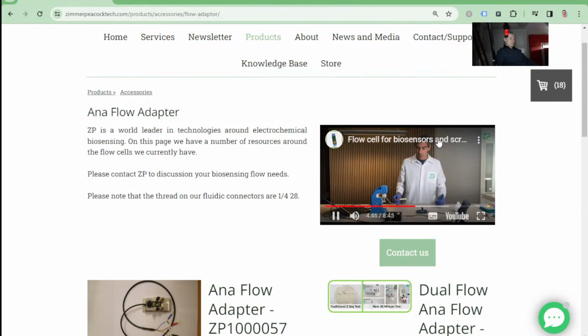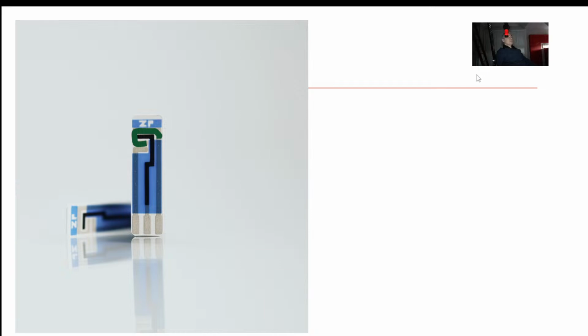So the quick answer to your question is most of our sensors, especially the ones we discussed today, including glucose, lactate, oxygen, sodium, potassium, urea, pH was in there as well, and I added ammonium in there, they're all able to be used in a flow cell. And yeah, the idea is that you would have a sensor in a flow system, flow the liquid over the top of it, and then have calibration routines. That's the way I would do it if I was trying to make a very accurate system.